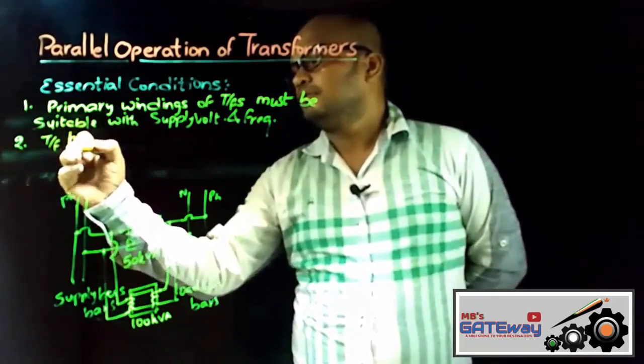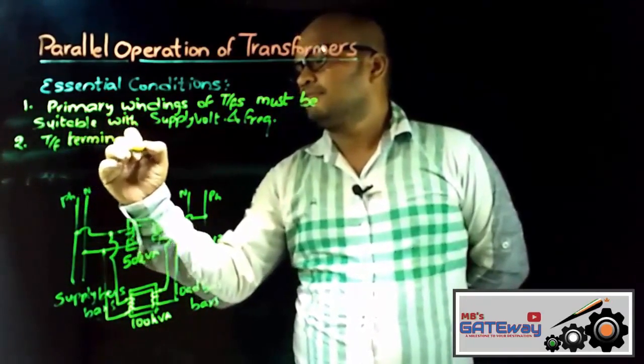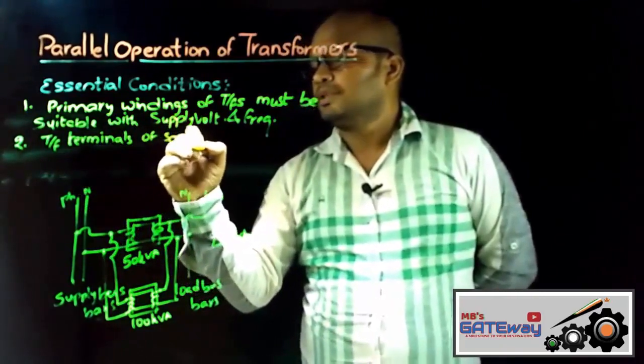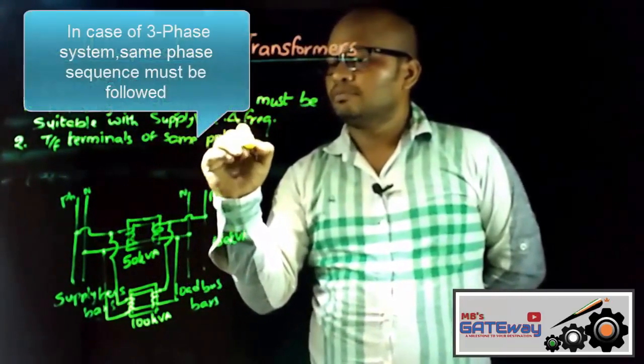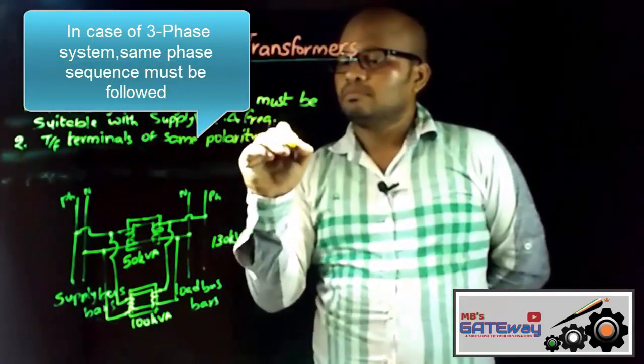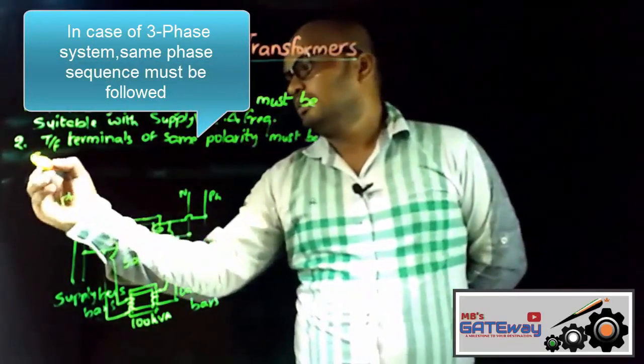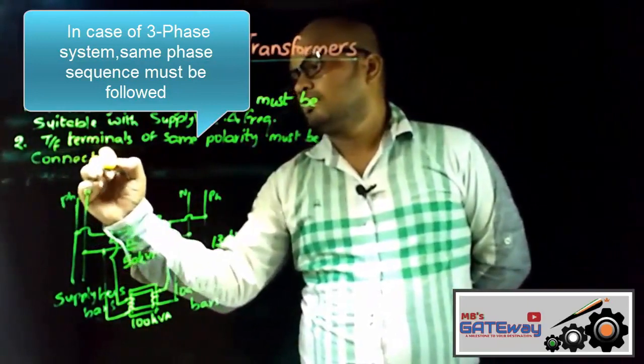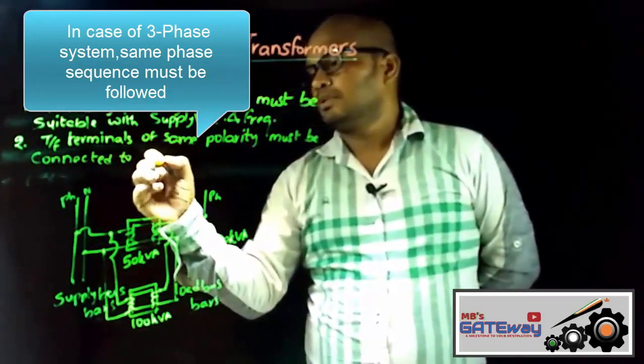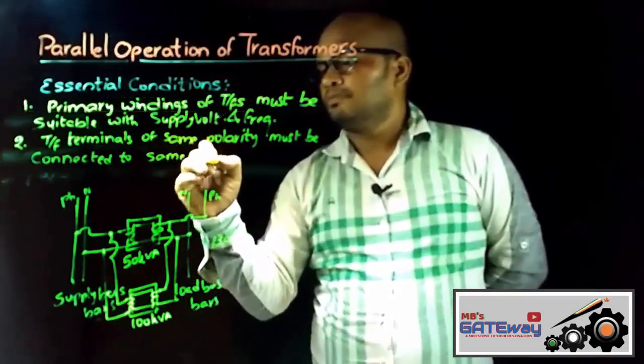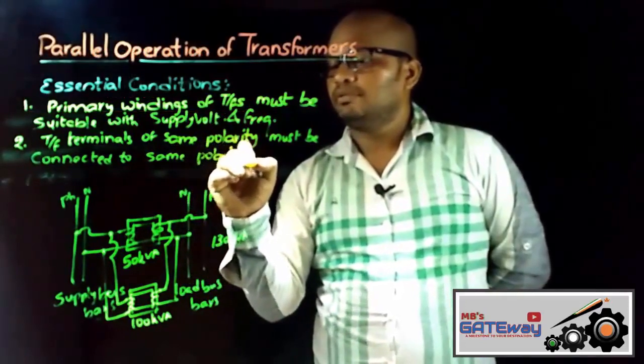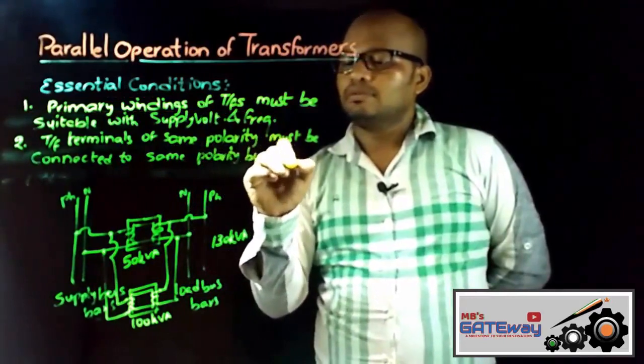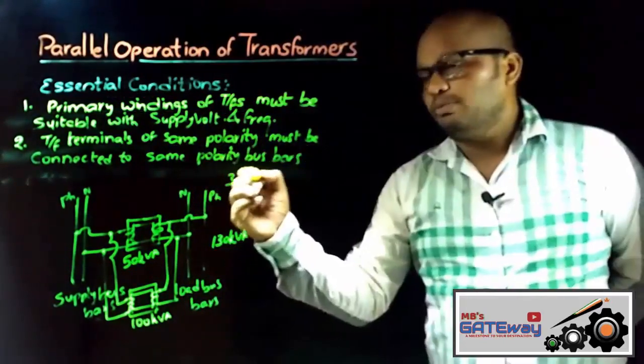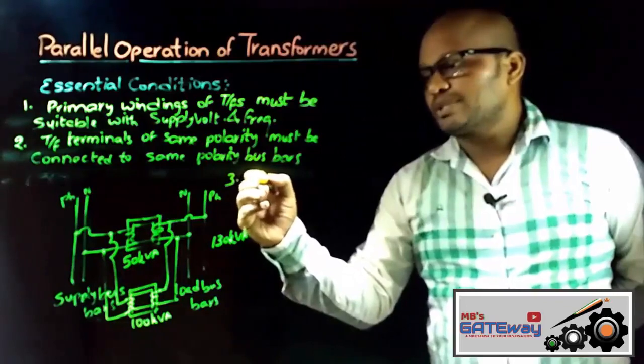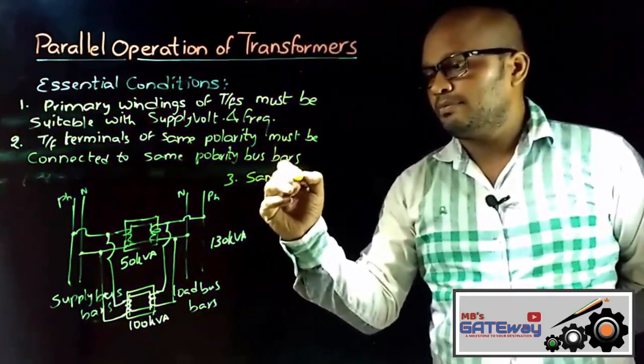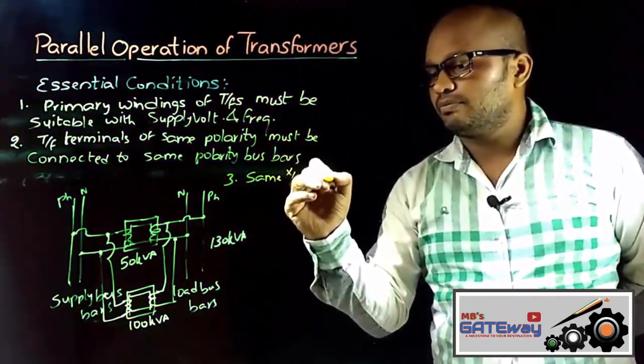And the second essential condition is that transformer terminals of the same polarity must be connected to the same polarity bus bars. And the third important condition is that transformers must have the same X/R ratio.